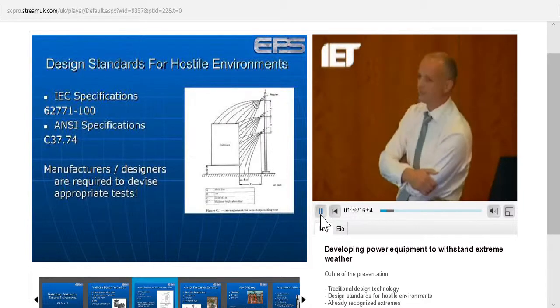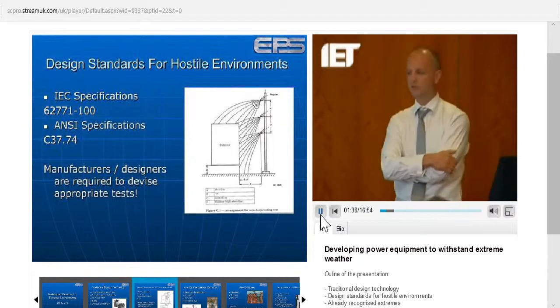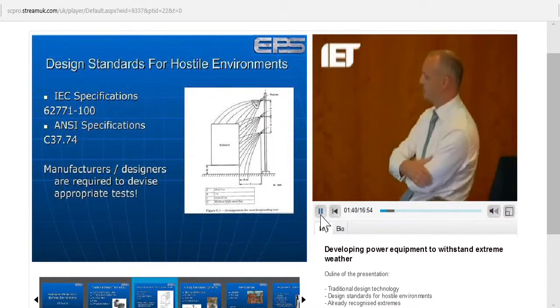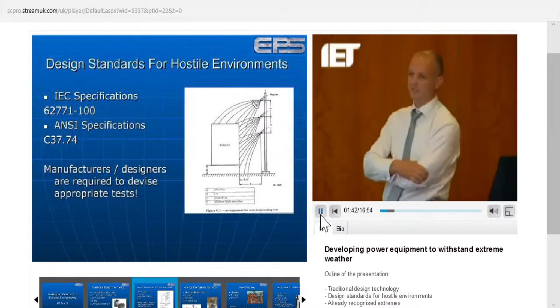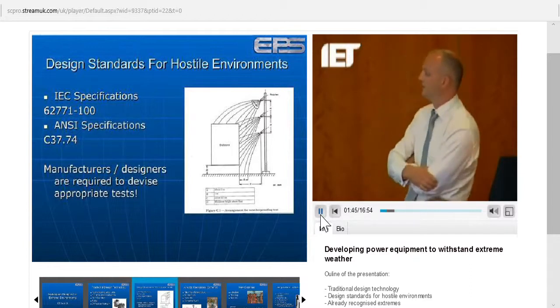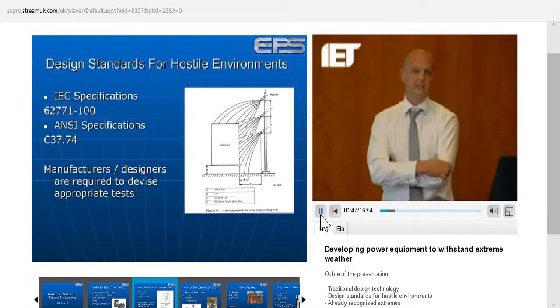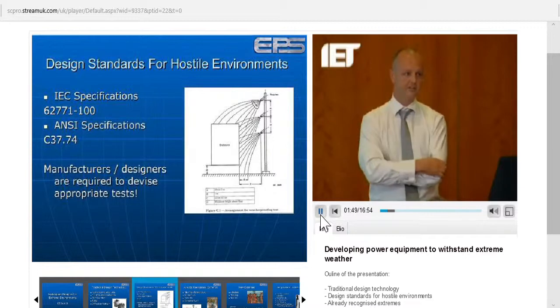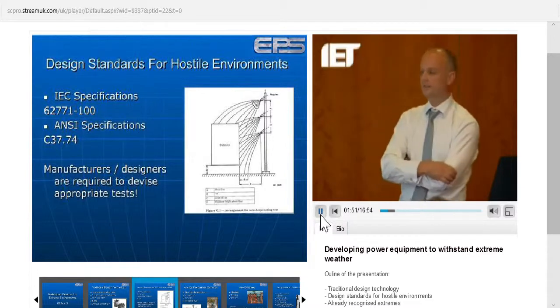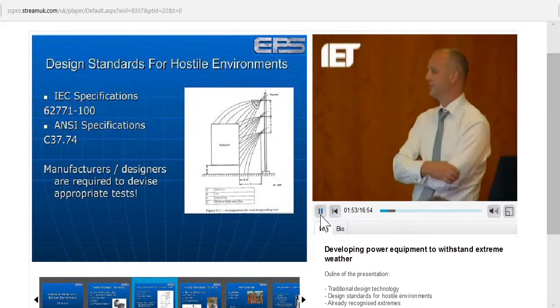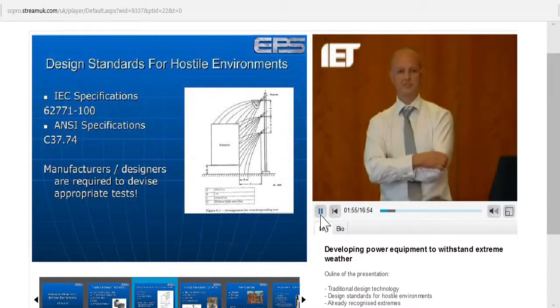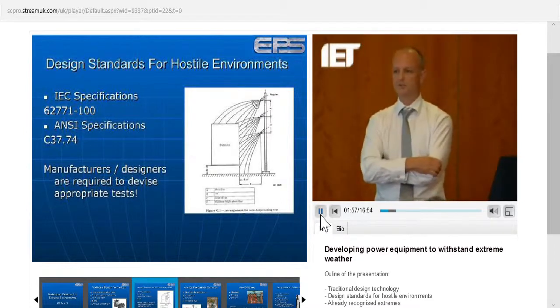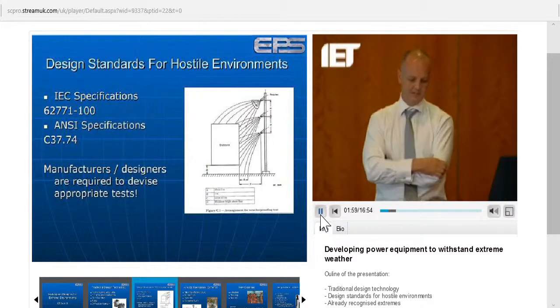If we look at what these specifications say about weatherproofing or floodproofing, IEC refers to a diagram showing the equipment being showered with water, and the equipment must sustain its voltage during that shower. ANSI instead states that the manufacturer must offer the purchaser some form of appropriate test results to back up their claim that the equipment is submersible or waterproof.